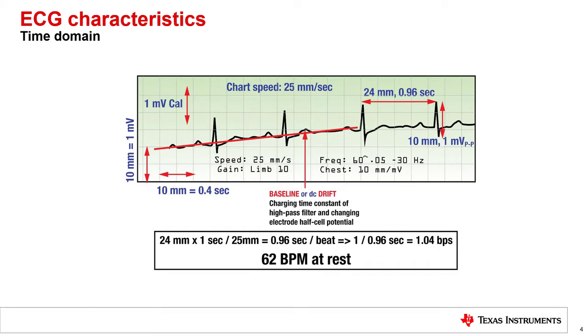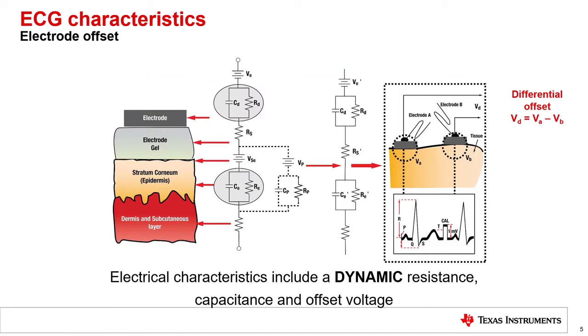This plot also illustrates one of the key challenges to measuring ECG: baseline drift. The baseline of an ECG develops between two measurement electrodes, which can change over time due to things like electrode contact quality, respiration, and patient movement. We can model the connection between the patient and the electrode like an electric circuit. Each layer of the skin provides some impedance, which is typically a complex impedance. The interface between the skin and the electrode itself also provides some complex impedance, plus some DC voltage. Finally, the electrodes generally have some DC voltage generated from their chemistry. These circuit elements cannot be modeled easily since they are actually changing constantly when the patient moves or if the electrode contact quality changes.